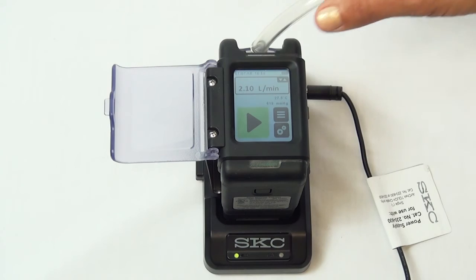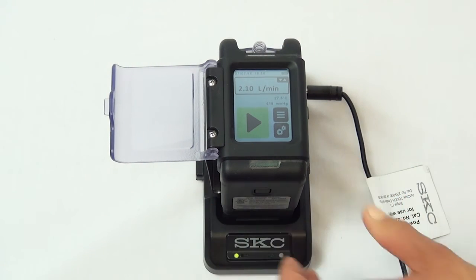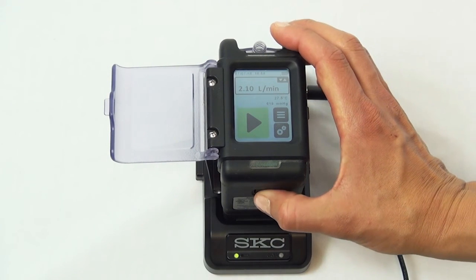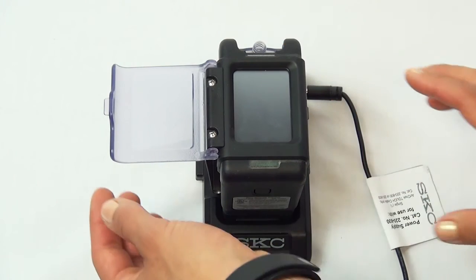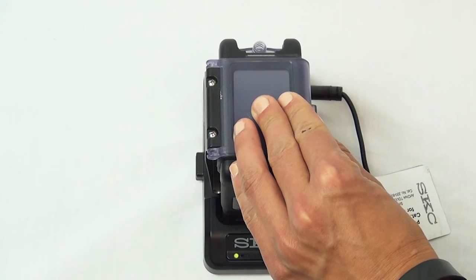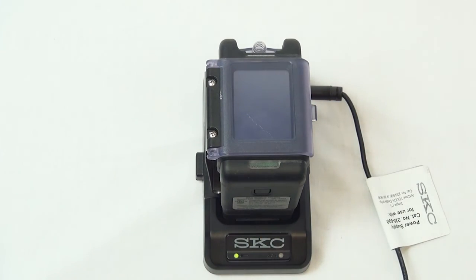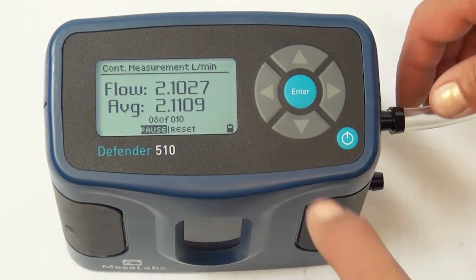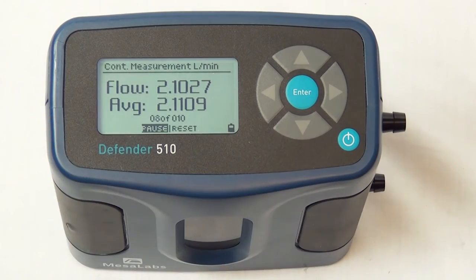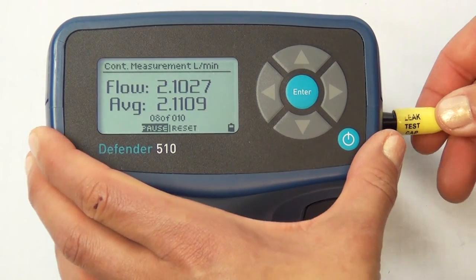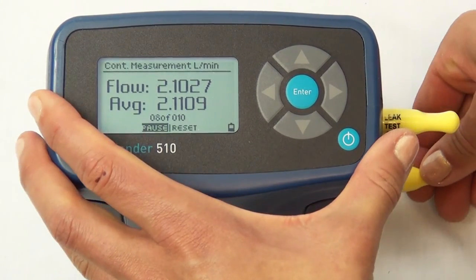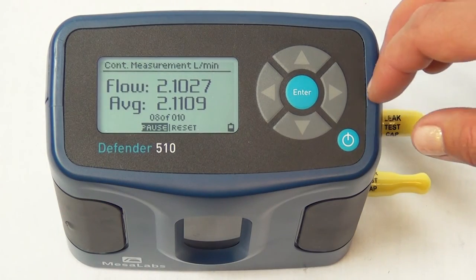After you are finished calibrating, disconnect the communication cable and the tubing from the pump and the calibrator. To turn the SKC AirChek touch pump off, press the square button on the front of the unit and close the screen cover. To turn the Defender off, ensure that the yellow caps are placed back on the barbed ports after use. Hold the power button down for 3 seconds.